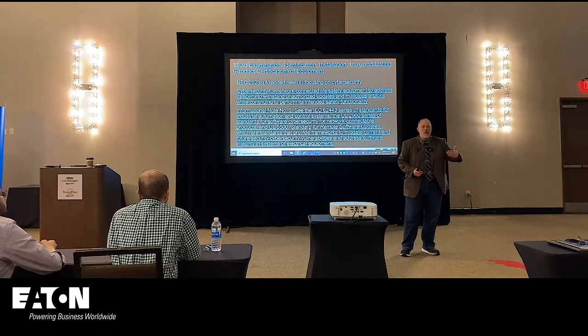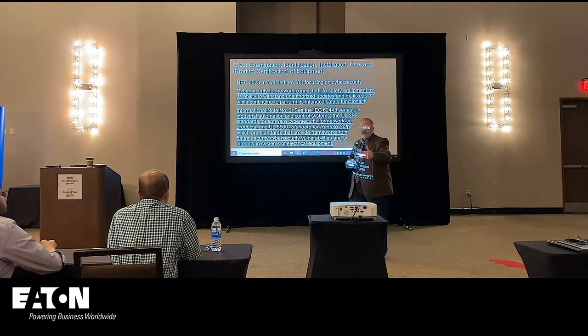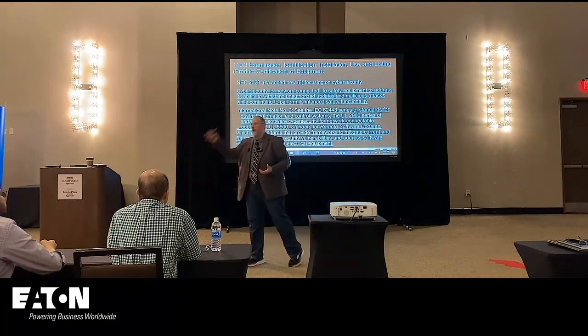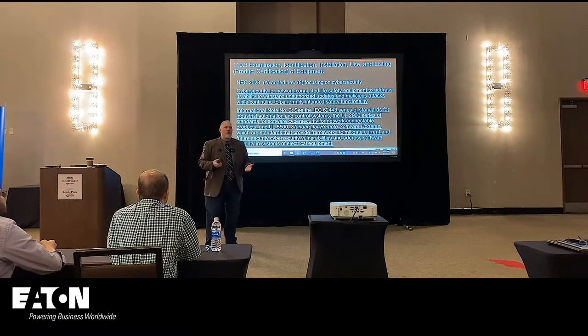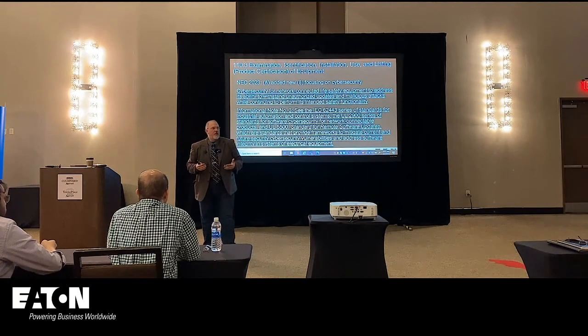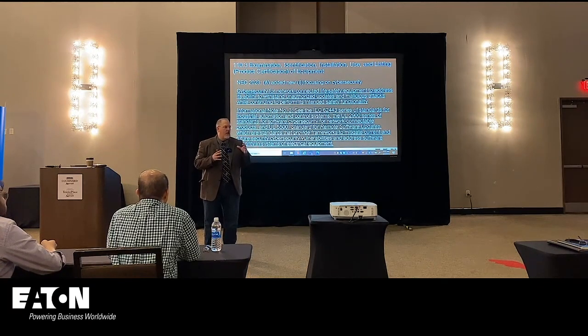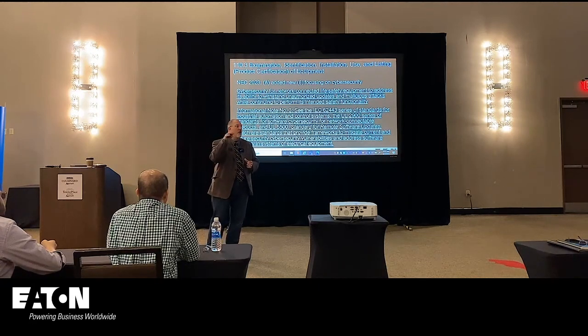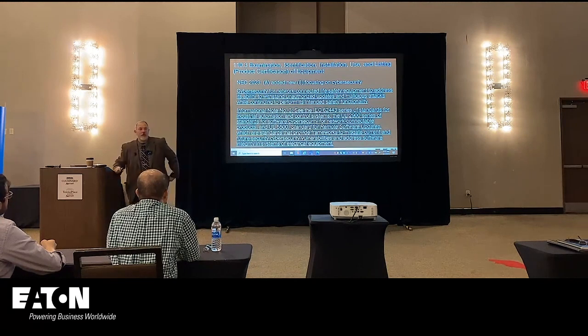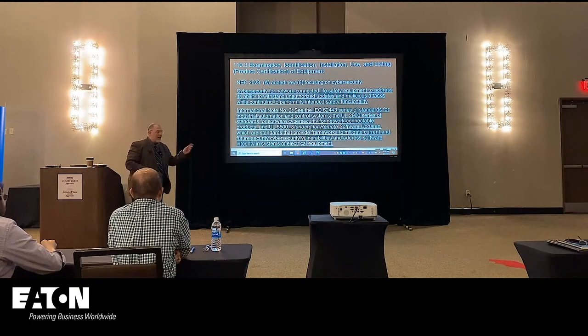So we have requirements in Article 240 for overcurrent protection devices that are network connected, where I can control the set points. We put it in Article 708, and I'll show you that language, which was, again, controversial, probably not applicable for the NEC. So this whole topic is in its infancy with regard to the NEC. It's already in NFPA 72 and many other NFPA documents. The general concern is we don't want someone to be able to take out a power distribution system maliciously because it's connected to the network. Now, if you talk to a cybersecurity expert, they'll tell you that doesn't address the internal threat, right? The bad actors don't have to be outside, they can also be inside. But in any case, it's getting recognition.